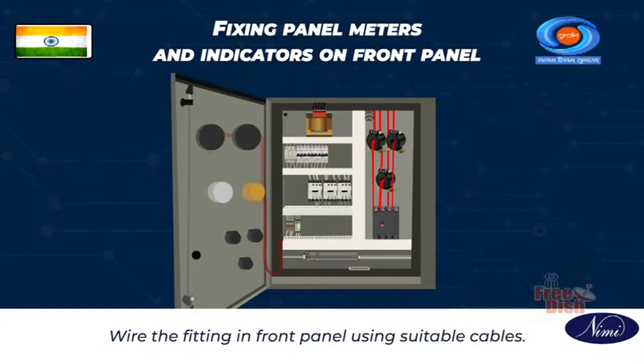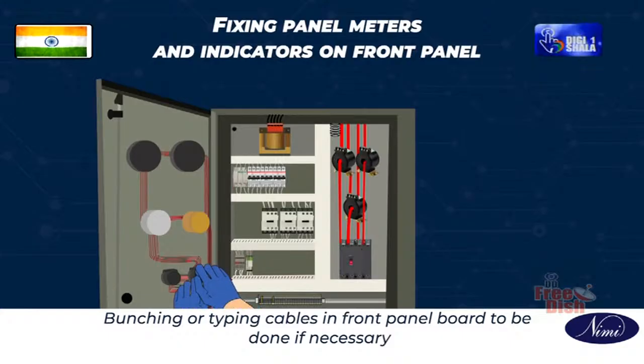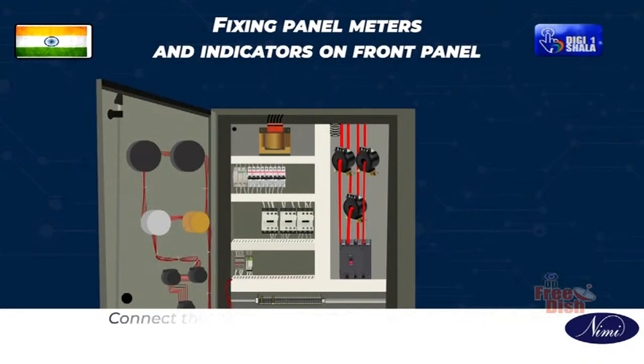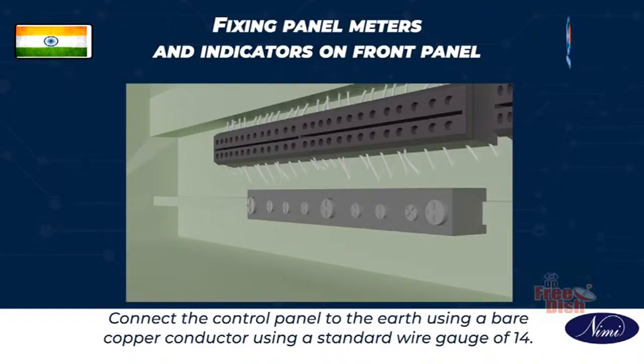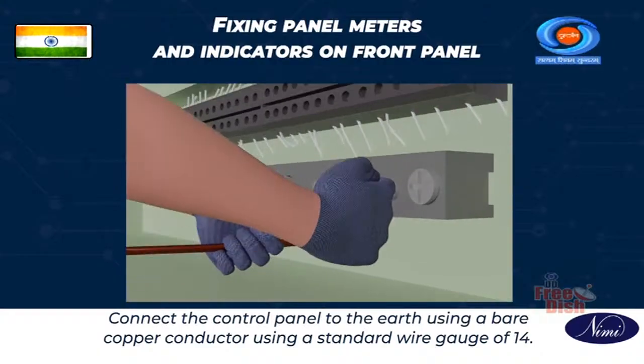Wire the fittings in the front panel using suitable cables. Bunching or tying cables in the front panel board is to be done if necessary. Connect the control panel to the earth using a bare copper conductor with a standard wire gauge of 14.